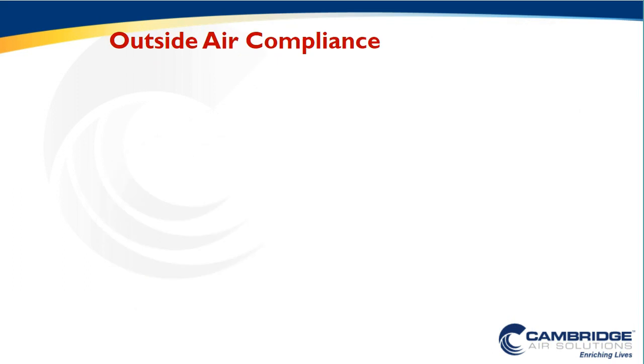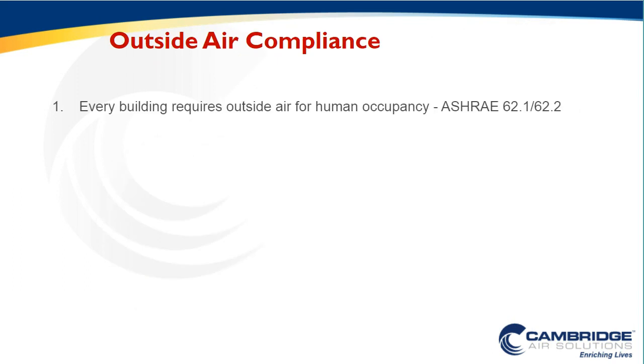And as engineers, and in the ASHRAE world, we know that every building must have outside air. We can't completely eliminate outside air from all buildings, and every building designed for human occupancy must bring in outside air and fresh air. And that's what the ASHRAE 62.1 standard does: it gives us a direction and a guideline for how much ventilation buildings need in order to meet safe indoor air standards.